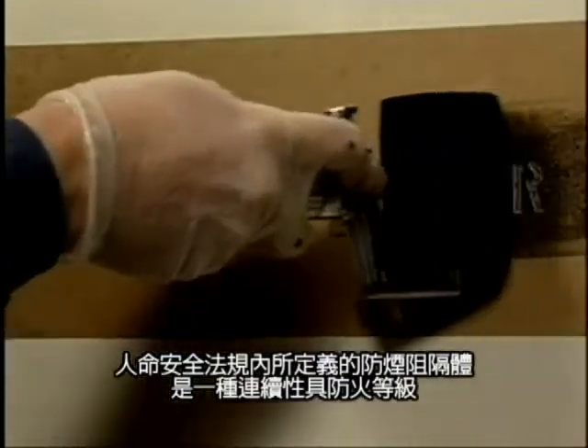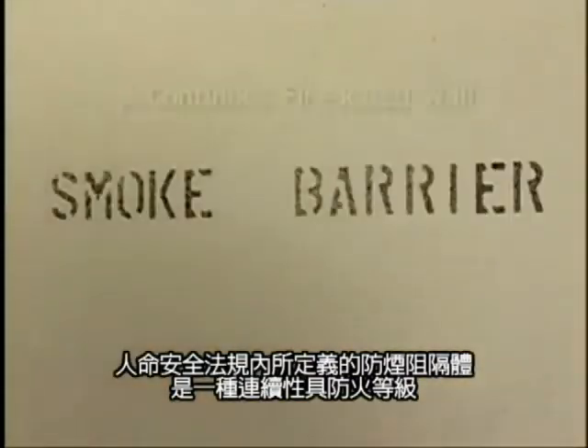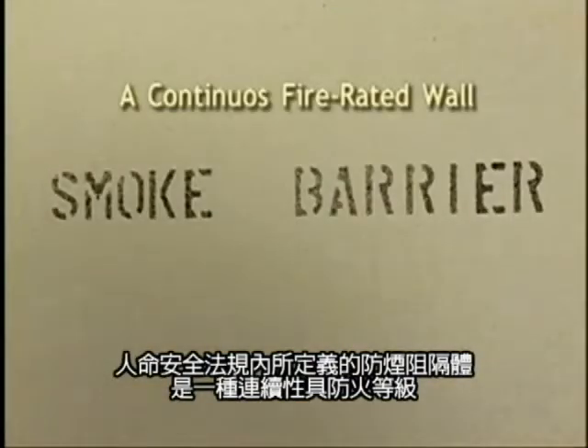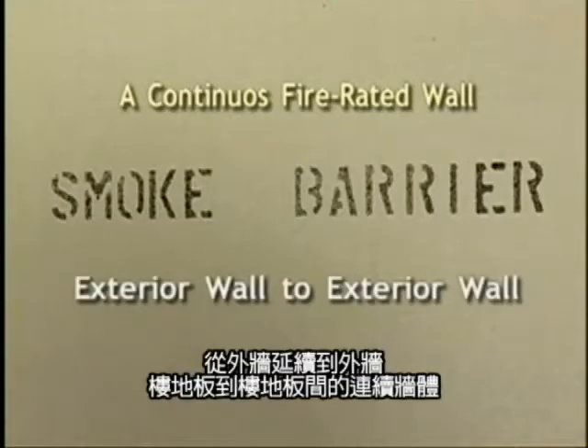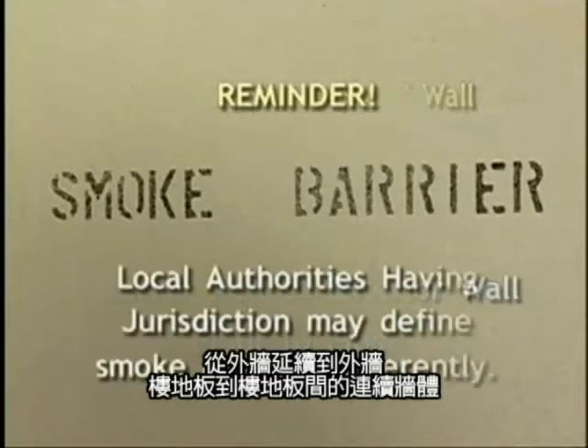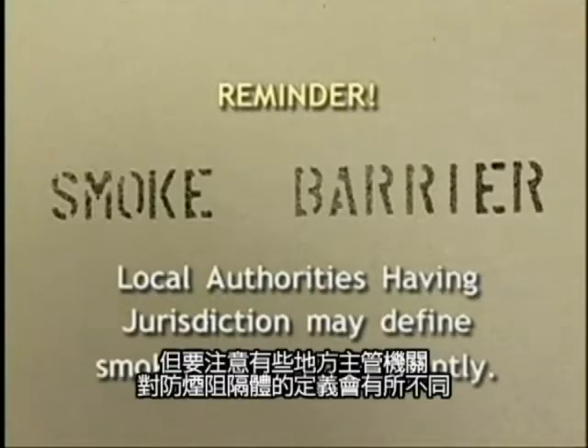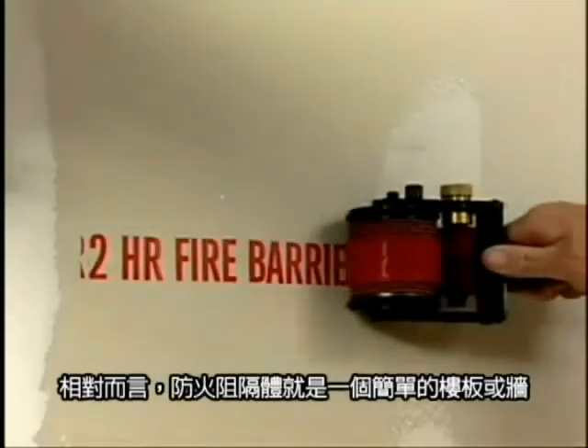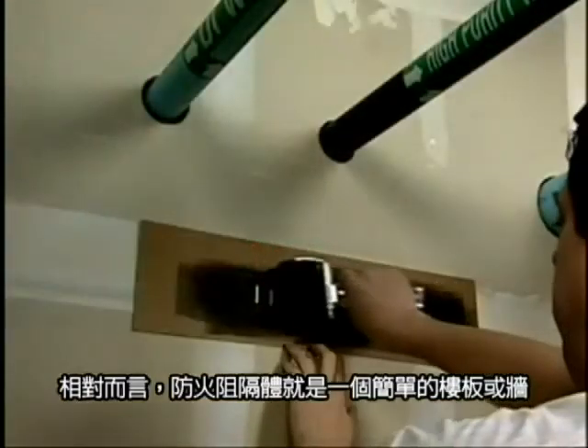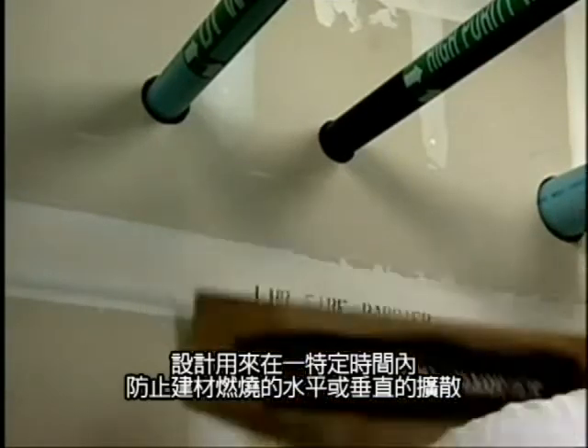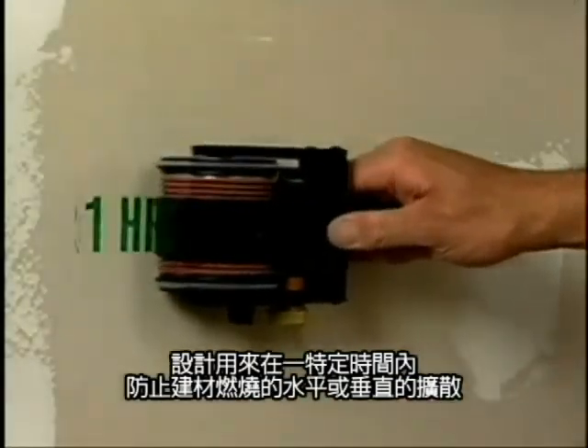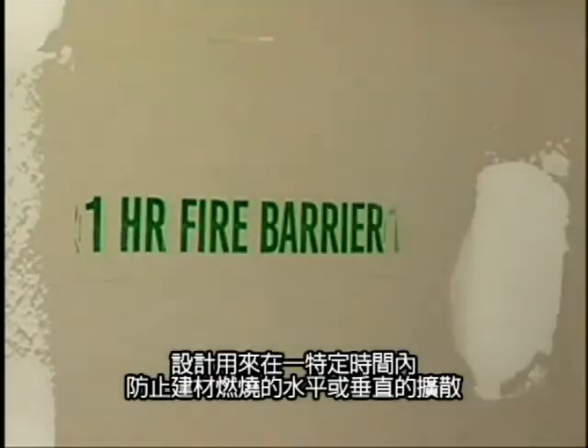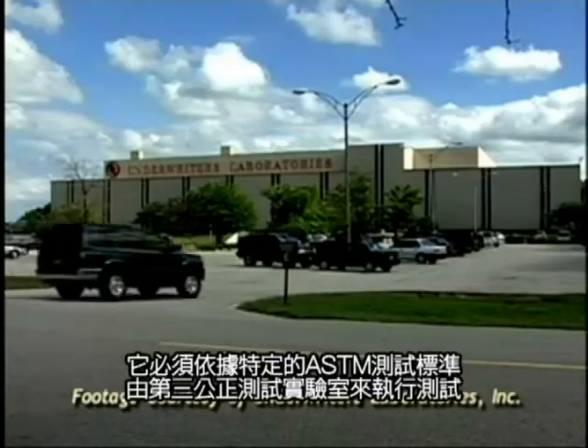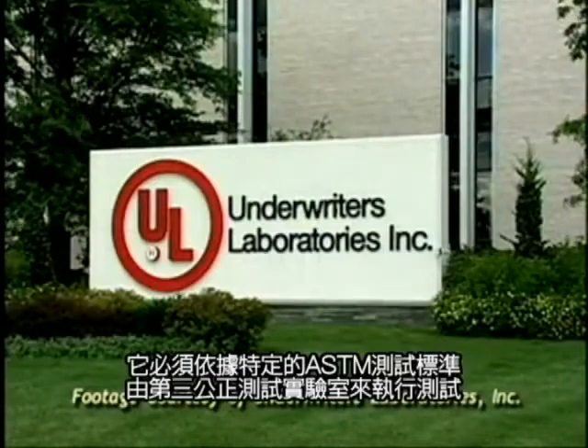A smoke barrier is defined by the Life Safety Code as a continuous fire-rated wall that extends from exterior wall to exterior wall and floor to floor. Be careful, however, because some local authorities having jurisdiction may define smoke barriers differently. A fire barrier, by contrast, is simply a wall or floor designed to prevent the products of combustion from spreading vertically or horizontally for a specific amount of time, and is tested by a third-party lab to specific ASTM test standards.